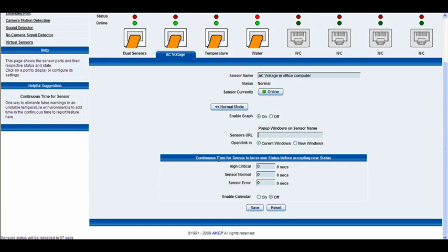Below that we have the continuous time — this is the duration the sensor must remain in a new status before that status is accepted. For example, if the sensor goes into a high critical status for five seconds, it will display that high critical status only once it has been in that status for the full five seconds. The same applies for the normal status and also for the sensor error.